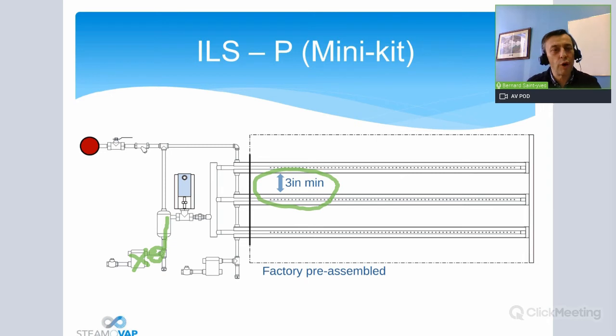This is what is called a flooded condensate line. Then all of this will be full of condensate, and you have a risk of bringing water out of the ramp. To avoid this, you put a thermostat here, and it will shut down the valve, so close the valve, in case the temperature here goes down, meaning that the condensate is coming up into the line. This works because there is a temperature difference between the steam and the condensate. This is how it is made.